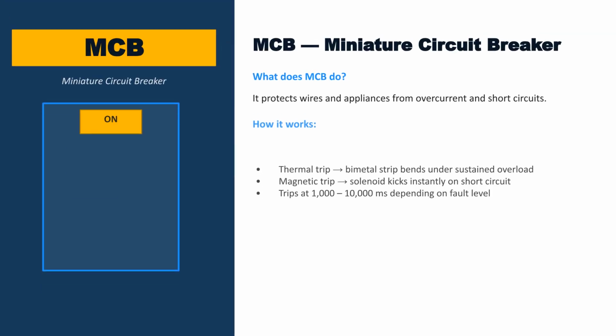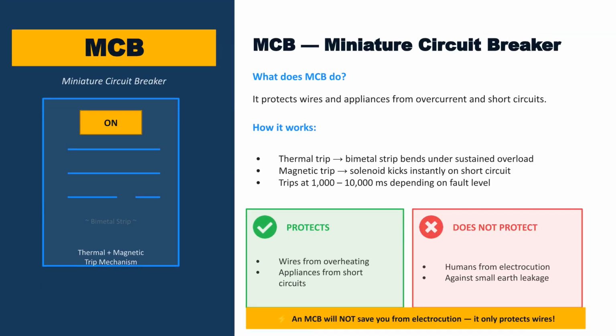The MCB protects wires and appliances from overcurrent and short circuits using thermal and magnetic trips. However, the MCB only responds to large currents like 6 to 63 amps. It will not trip on the small but deadly 30 milliamps leakage. An MCB protects wires, but it does not protect humans.